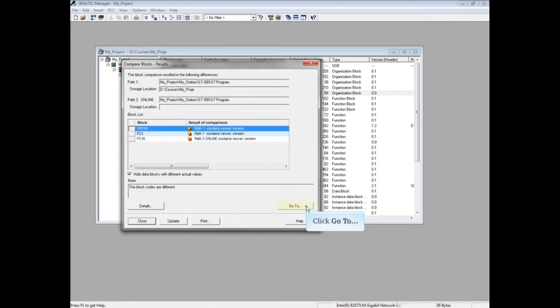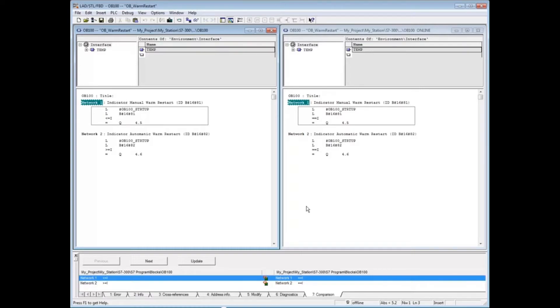Make sure that OB 100 is highlighted and click the Go To button. This opens a detailed side-by-side view of the blocks. The offline block is on the left and the online block is on the right. If you look in the comparison tab at the bottom of the program editor, it tells you that in Network 1 of this statement list code, the offline block contains the command less than or equal to as integers.